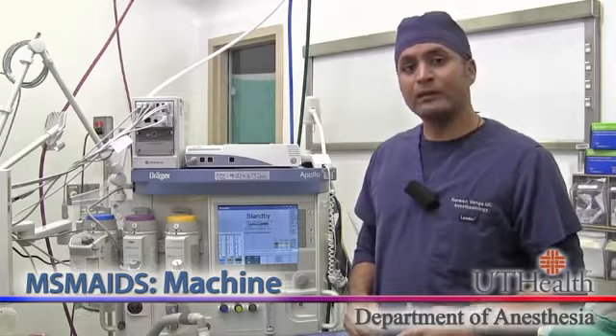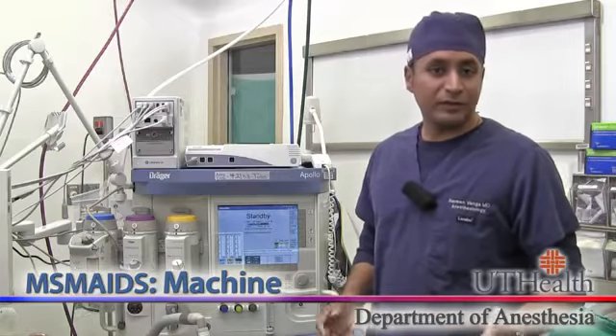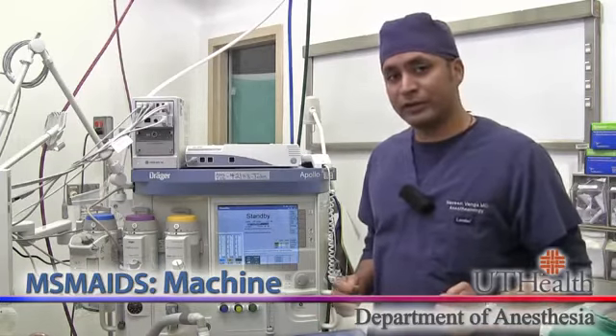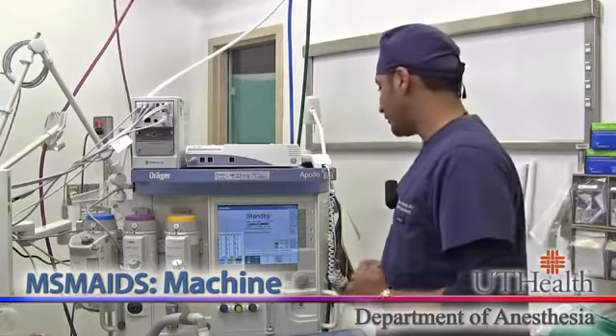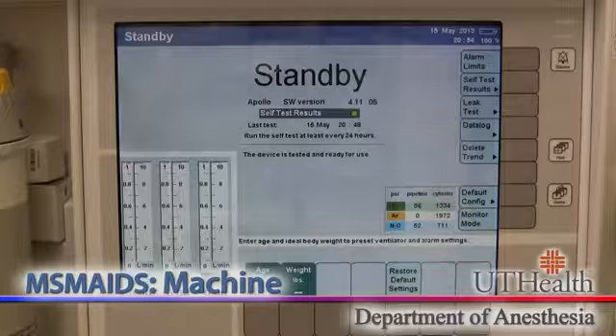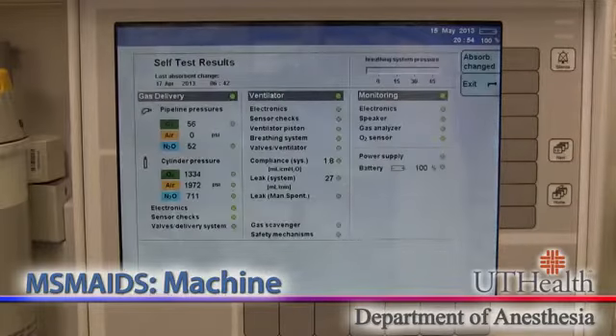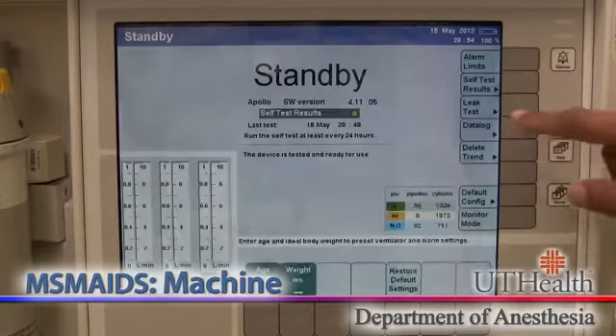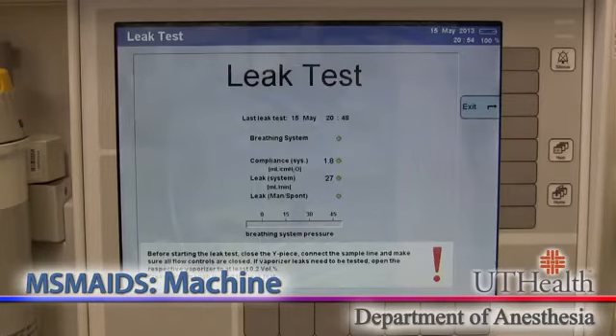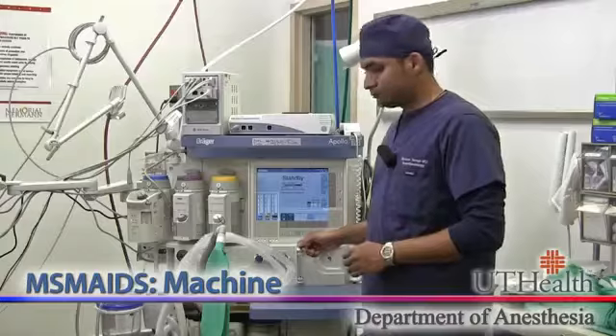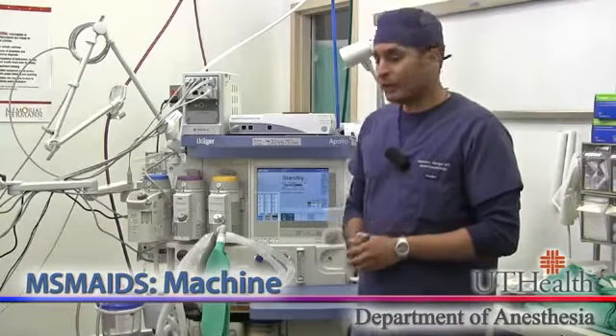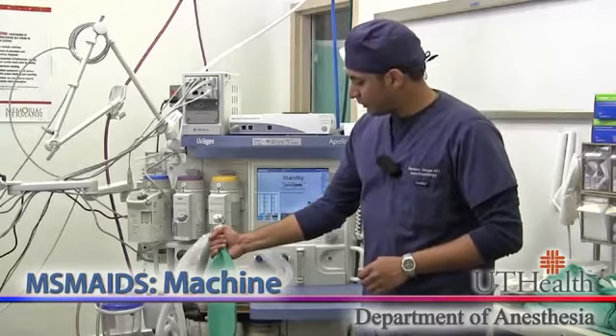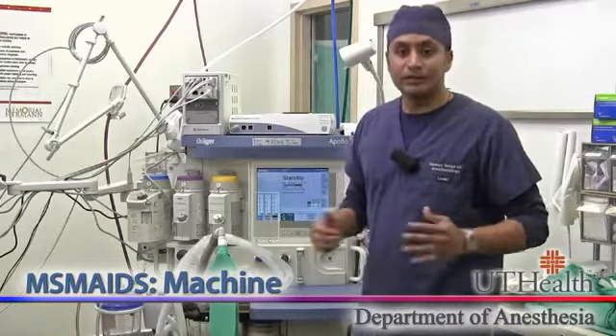Depending on your machine, you may have to run additional tests, such as an oxygen calibration test or a negative pressure test. Fortunately for us, this machine automatically does all these tests. Now, this machine runs its own diagnostics. It's going to tell you the last time it did a test and give you the results of that test. It's also going to give you the information about the last leak test that it performed, when, and the results of it. Last of all, make sure you have a circuit and a bag attached to the machine. And that completes the machine part.